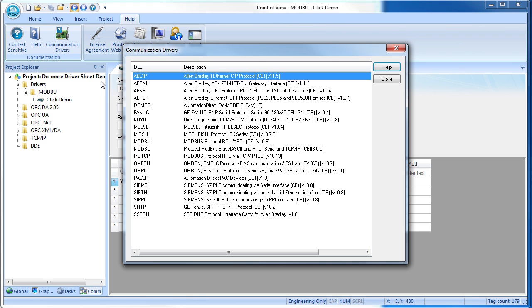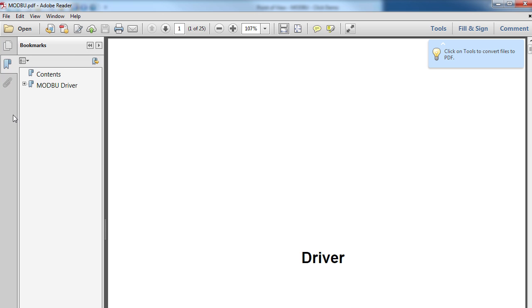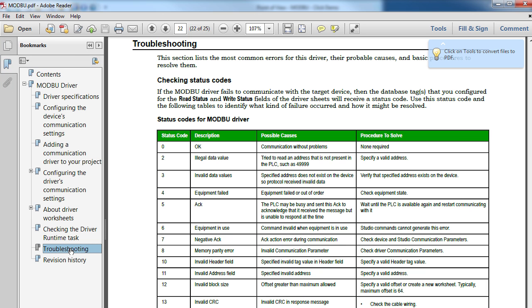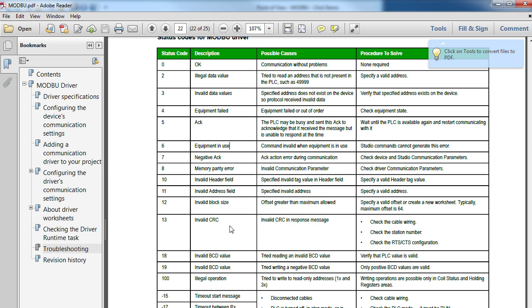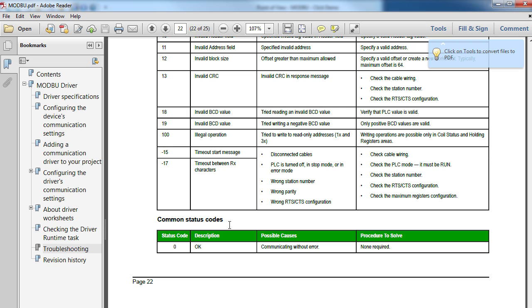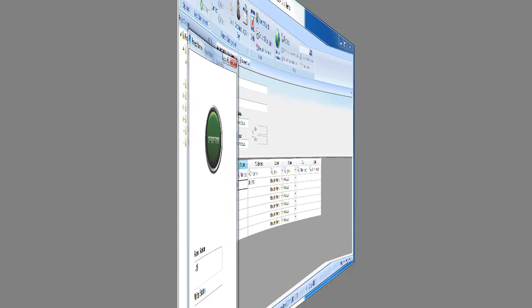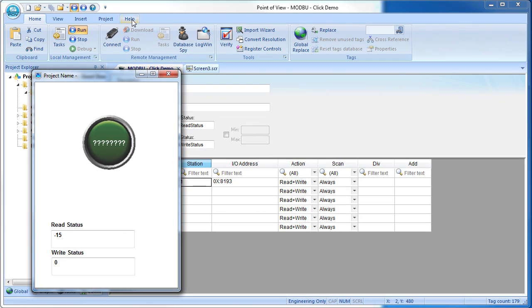To decode that, we go to Help, communications drivers, Modbus driver. Go to the troubleshooting section and scroll to error minus 15. Looks like we are getting a timeout, and the chart gives us several things to look at, one of which is the wrong station number. Exactly what we did. So you can see how incredibly important it is to keep an eye on those status messages. They do a great job of identifying the issue and help you get up and running quickly.